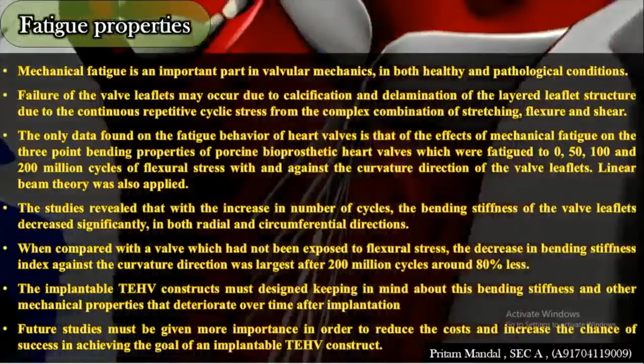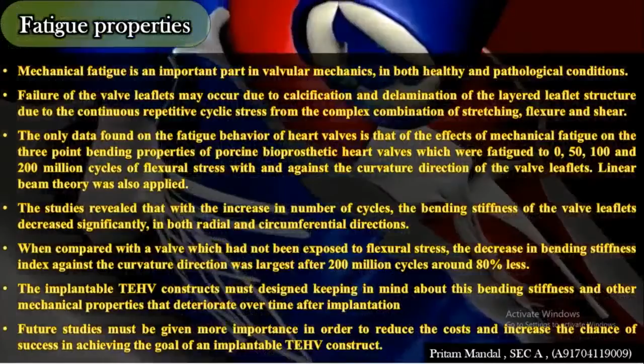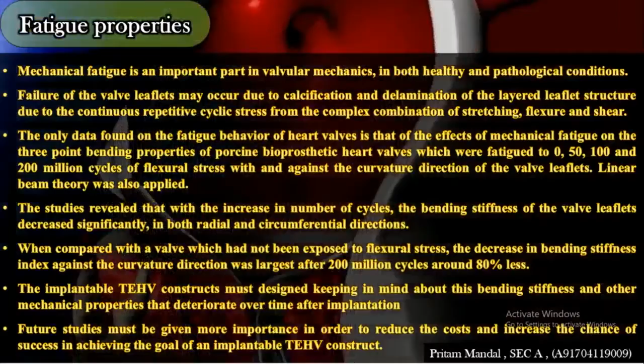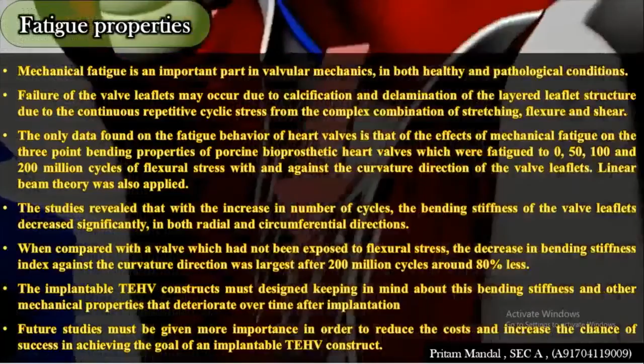These valves were fatigued to 0, 50, 100 and 200 million cycles of flexural stress with and against the curvature direction of the valve leaflets. In this, linear beam theory was also applied. The studies revealed that with the increase in number of cycles, the bending stiffness of the valve leaflets decreased significantly in both the radial and circumferential directions. When compared with a valve which had not been exposed to flexural stress, the decrease in bending stiffness index against the curvature direction was largest after 200 million cycles, around 80% less.